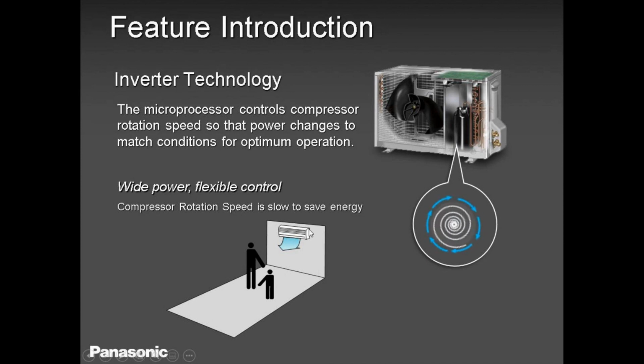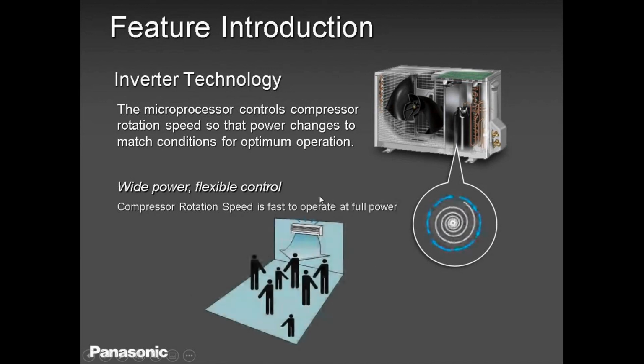So everybody talks inverter technology, inverter technology, inverter technology. What is this inverter technology about? Well, it's a microprocessor in there, inside that PCB over there, that is embedded. That microprocessor is just like our brain. So when our brain gets the information what to do, we act. Same thing with this microprocessor. It gets the information from the sensors, the indoor sensors, the outdoor sensors. Depending on what the sensors are telling it and what your remote controller setting is, that compressor is going to work accordingly.